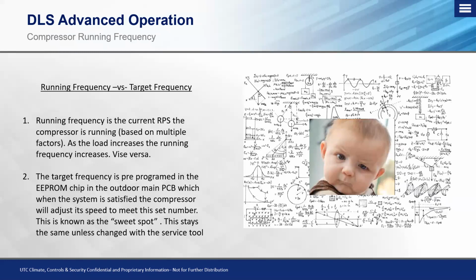There's a lot of different factors that the outdoor unit or the control looks for to determine what the running frequency of that compressor is going to be. But for us as service techs, understanding that number is essentially looking at that number, and that's the speed of the compressor. So as the load increases, the number increases. As the load decreases, the number decreases.